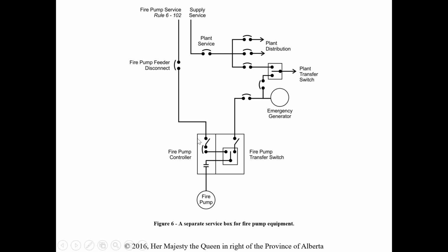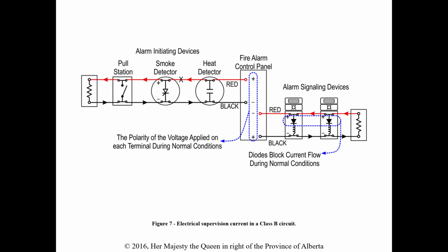Go through all the disconnecting means, overload. We don't need overload protection for that pump motor because we basically don't want it to trip on overload. We just want it to run as long as possible. So definitely go through that as well too. We don't need ground fault protection on a fire pump because we, again, don't want that to turn off. So definitely go through those code rules.